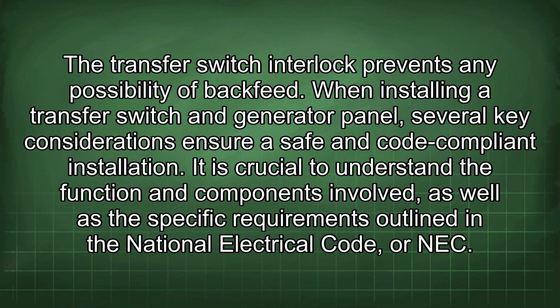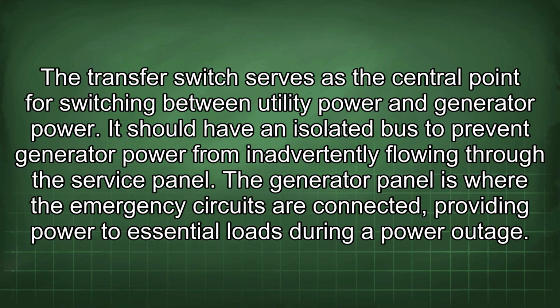When installing a transfer switch and generator panel, several key considerations ensure safe and code-compliant installation. It is crucial to understand the function and components involved, as well as the specific requirements outlined in the National Electrical Code, or NEC. The transfer switch serves as the central point for switching between utility power and generator power. It should have an isolated bus to prevent generator power from inadvertently flowing through the service panel. The generator panel is where the emergency circuits are connected, providing power to essential loads during a power outage.